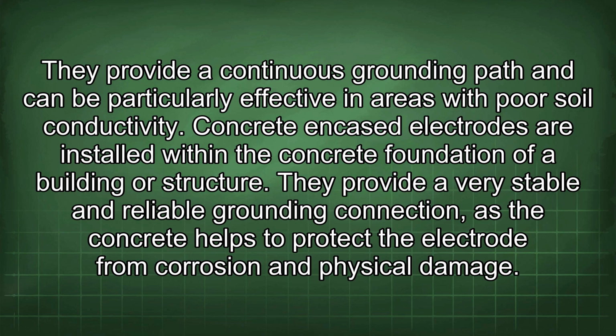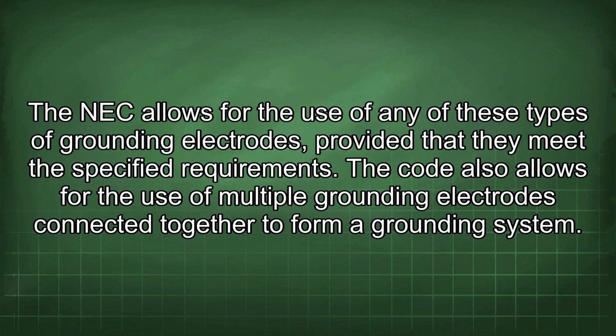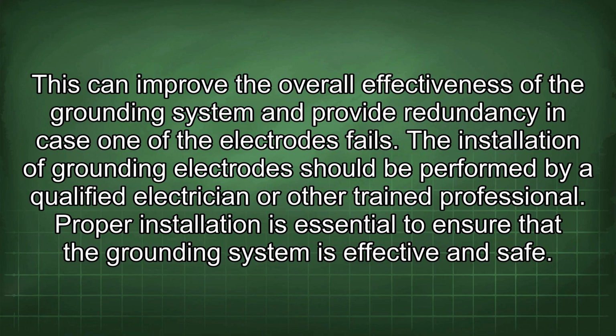Concrete encased electrodes are installed within the concrete foundation of a building or structure. They provide a very stable and reliable grounding connection as the concrete helps to protect the electrode from corrosion and physical damage. The NEC allows for the use of any of these types of grounding electrodes, provided that they meet the specified requirements. The code also allows for the use of multiple grounding electrodes connected together to form a grounding system. This can improve the overall effectiveness of the grounding system and provide redundancy in case one of the electrodes fails.